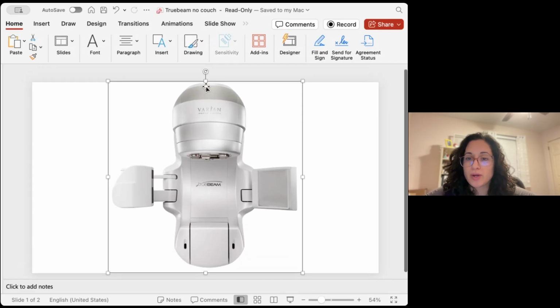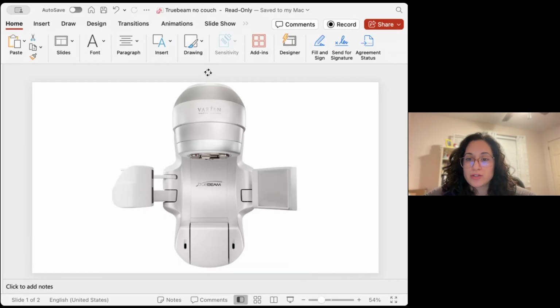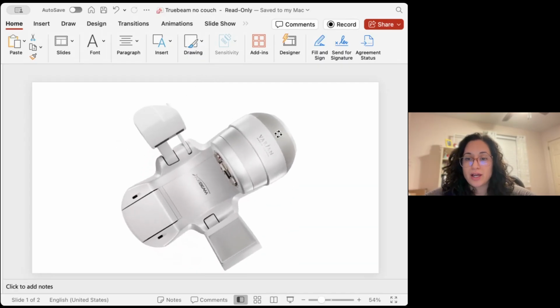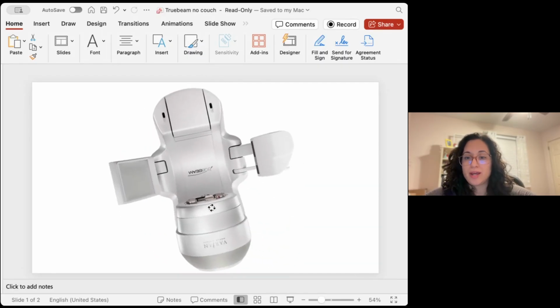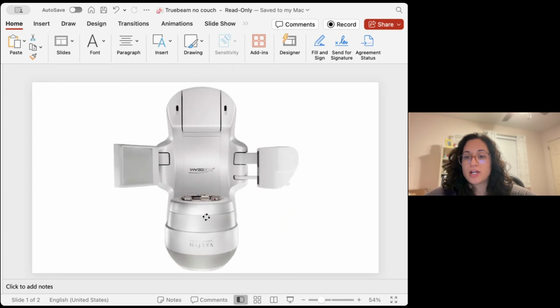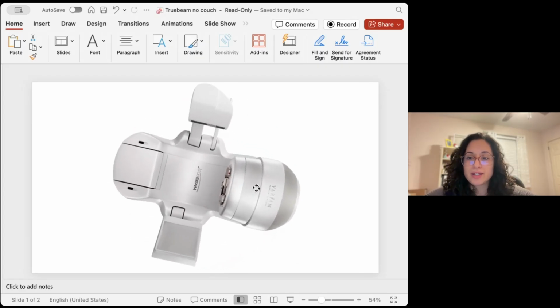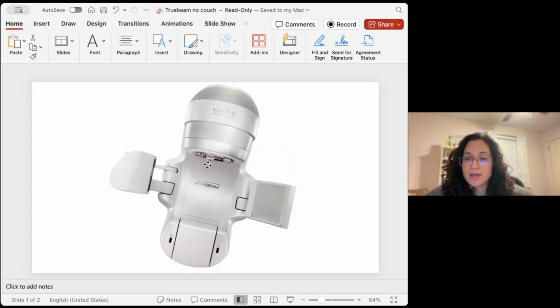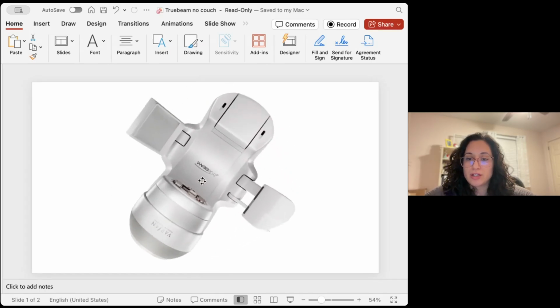So these are some common questions we might see during our radiation therapy schooling and maybe even the registry. So the gantry can move clockwise. If we're looking at the machine from the foot of the table, it's going to move to our right, down in the clockwise position, and it can go all the way underneath the patient to about 179 or 180 degrees. It can't move past this part because there are some limitations within the machine. So it would have to come back counterclockwise and then rotate around the patient on the other side.